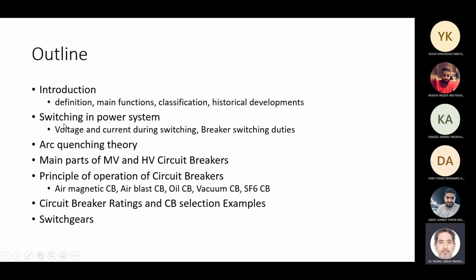Then I'll go to the switching in power systems, how the current and voltage look when a breaker opens circuits. Then we'll come to what is important: the arc quenching theory, how the circuit breaker gets rid of the arc. Then we'll go over the main parts of a circuit breaker for high voltage and medium voltage applications. I'll then go to the working principles of some of the breakers, like air magnetic circuit breakers.